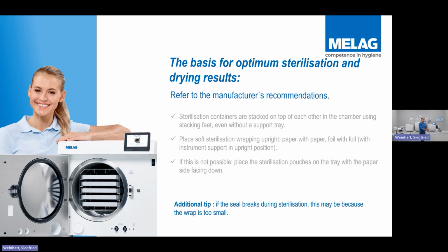If you have overloaded that with instruments, what can happen is as that pouch breathes, you can get perforations in the back, or you could get perforations in the top where it opens up. As soon as it opens up, you've not got a correctly sealed, correctly sterilized instrument. Also, the paper element here, bearing in mind you've got steam in this chamber, will get wet, and that will mean that paper will rip a lot easier when that instrument comes through. So it's really important that we don't overload the pouches, okay.